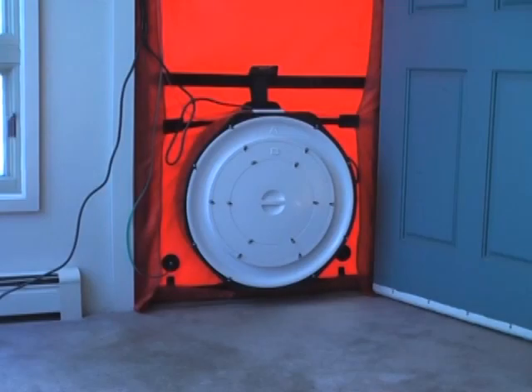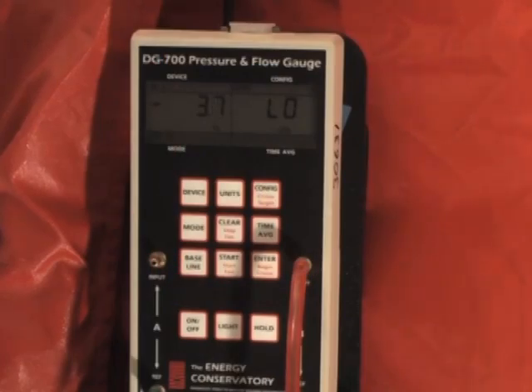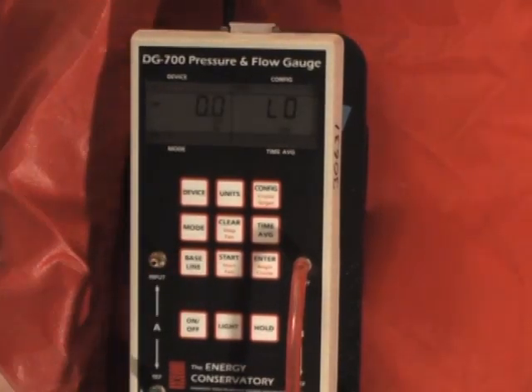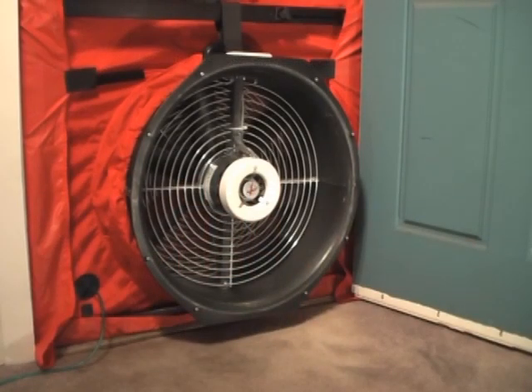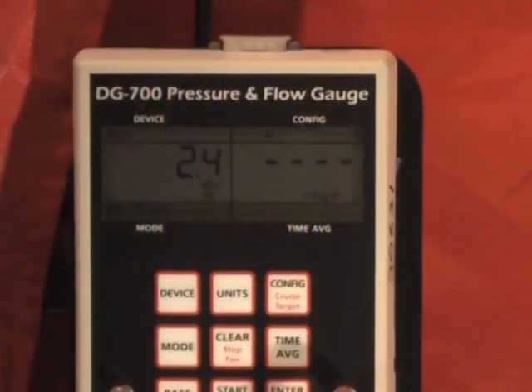Baseline pressure is always measured with the fan completely covered. Baseline pressure will fluctuate—it will fluctuate more during windy conditions. Once the adjusted baseline procedure has been completed, the pressure display on channel A should fluctuate around zero. When the fan cover is removed or the desired ring is installed and the fan remains off, the measured pressure will change again. This is normal.